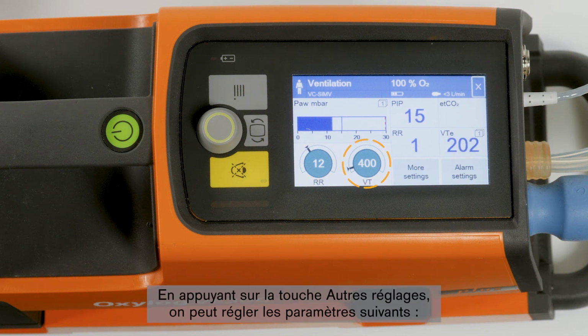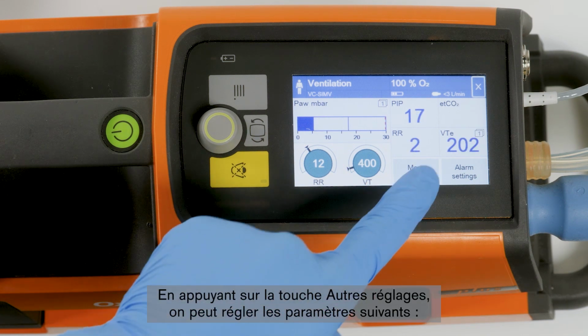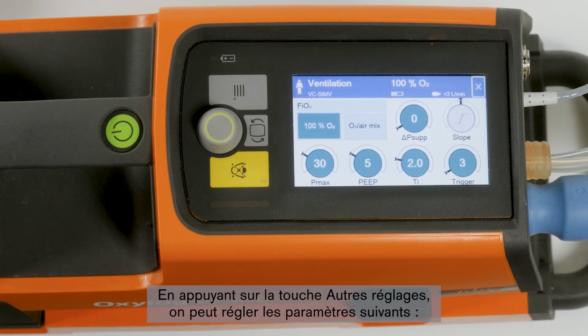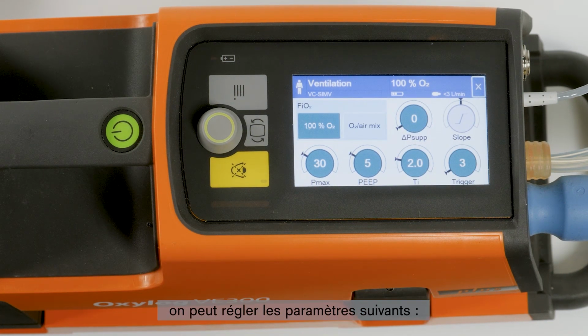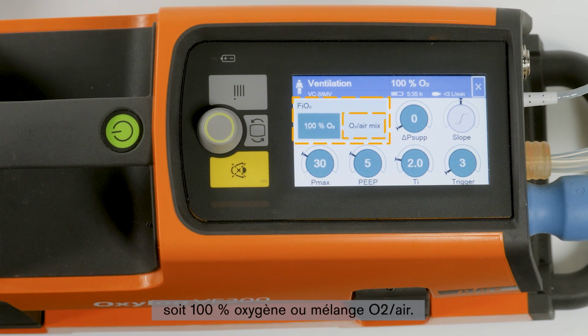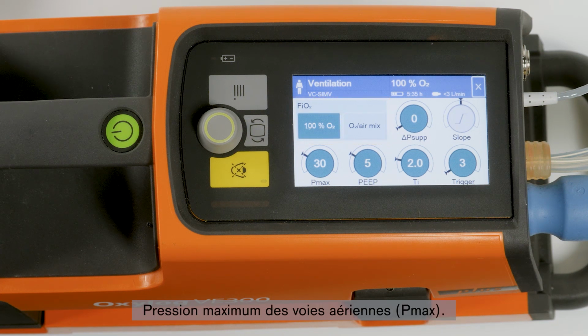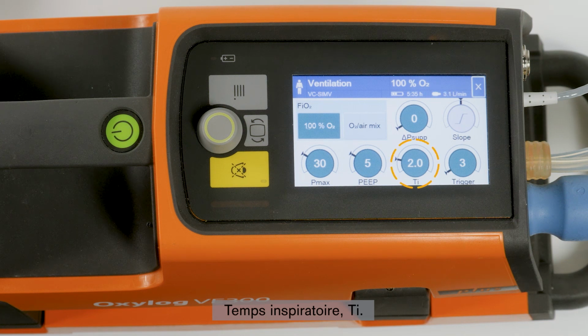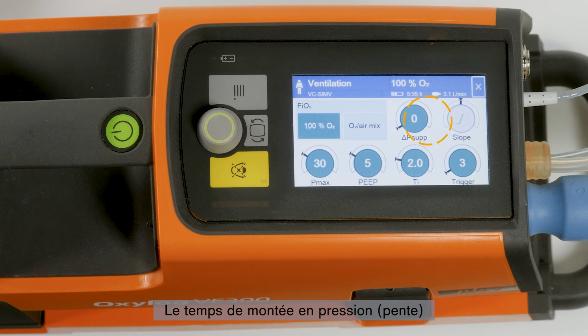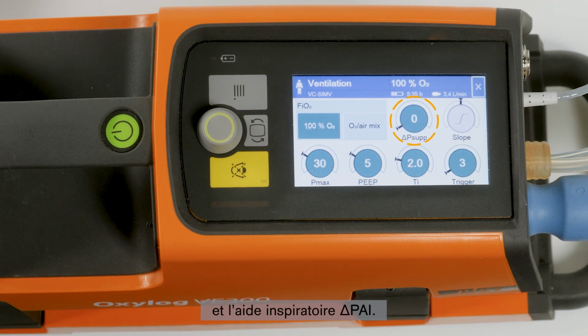By pressing the More Settings button, further parameters and settings can be adjusted. The following parameters and settings can be adjusted. The inspiratory oxygen concentration FiO2, either 100% oxygen or oxygen air mix. The maximum airway pressure, Pmax, the positive end expiratory pressure, PEEP, the inspiratory time, TI, the trigger sensitivity, trigger, the pressure rise time, slope, and the pressure support, delta P supp.